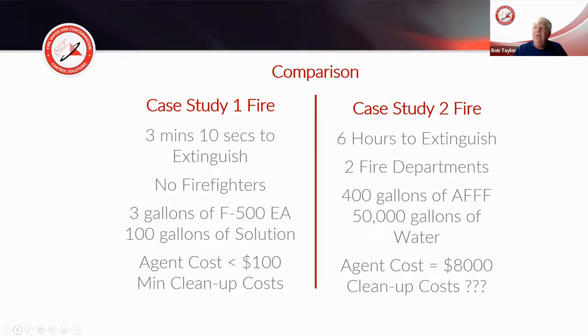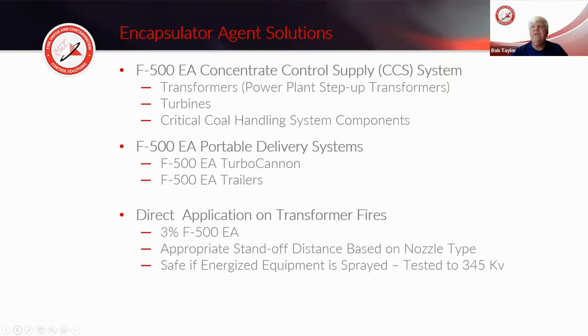Compared to another similar facility, similar in design and size of equipment: 6 hours to extinguish, 2 fire departments, 400 gallons of AFFF, 50,000 gallons of water, somewhere around $8,000 just for AFFF cleanup, and who knows how much for all the water that had to be contained and cleaned. So spending a little bit up front to be prepared pays off hugely should something ever develop.